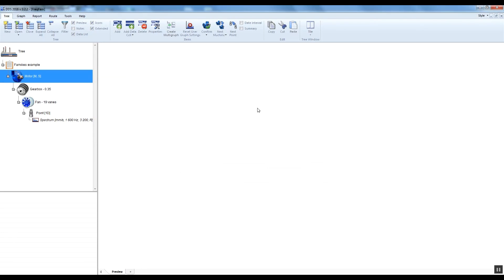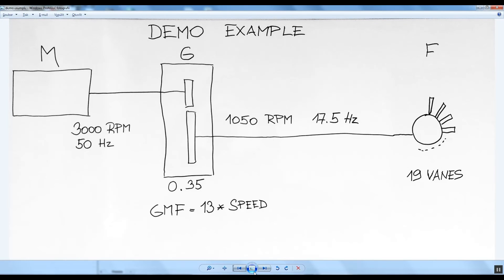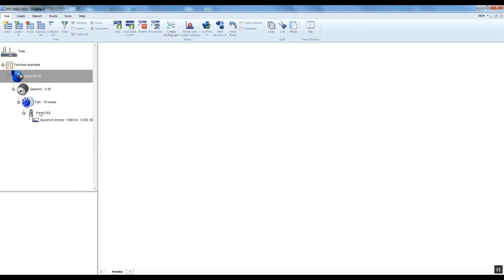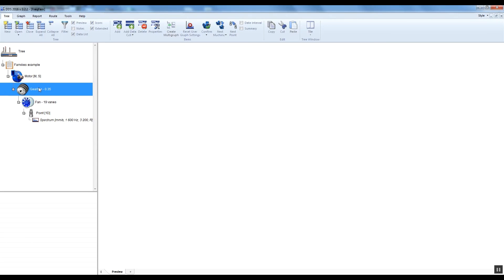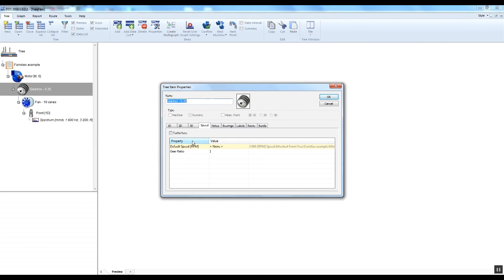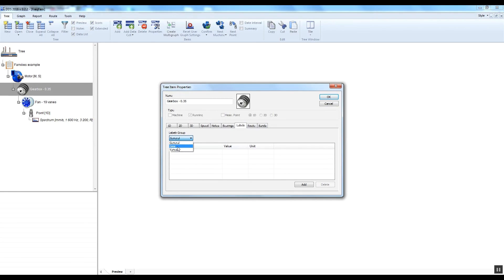The gear ratio is 0.35 and gear mesh frequency is 13 times the speed. I select the gearbox and open the gearbox properties and the speed tab. The default speed contains the information that the speed of 3000 RPM is inherited from the motor. Now I enter the gear ratio 0.35. Now I select the labels tab and select the gear labels group.